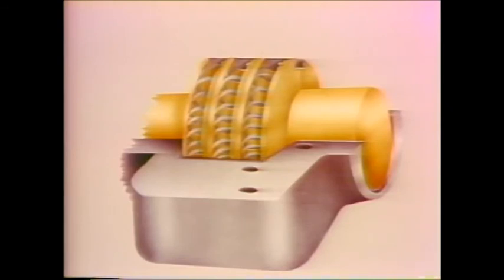A carbon seal system consists of one or more carbon rings held in place against the shaft by springs. As the shaft turns, it rubs against the carbon rings, and an effective seal between the shaft and the casing is achieved. Carbon, being softer than metal, creates minimal wear on the turbine shaft. Now, eventually, the carbon wears down, so the carbon rings must periodically be replaced.